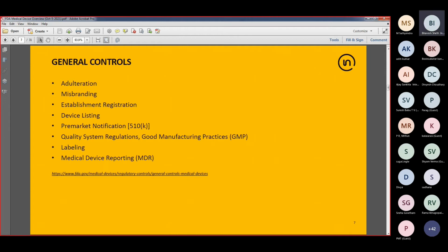Quality system regulations, good manufacturing practices also fall into this category, unless, of course, if there is a class 1 device that is exempt from good manufacturing practice regulation. There are a few devices that are exempt from GMP, but not all of them. Most of the devices do require some or the other compliance with quality system regulations and good manufacturing practices. General labeling guidelines also fall under the category of general controls. And finally, medical device reporting. There is a lot of emphasis on reporting events, adverse events, and complaints related to medical devices. So those requirements are applicable regardless of the device class.